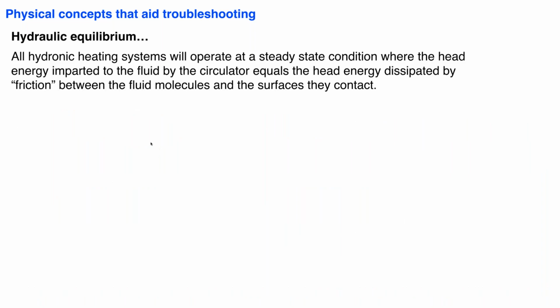We have circulators that are imparting mechanical energy to the water. We call that mechanical energy head. You know, it's a term that's been around the hydronics industry for a long time. And sometimes people say, well, head is equal to differential pressure. And actually, that's not true. Head is simply a word that describes a form of mechanical energy that a circulator imparts to water. And as that water moves through the system, everything it comes in contact with, even between the molecules of H2O, there's a frictional effect that is dissipating mechanical energy ultimately into heat.